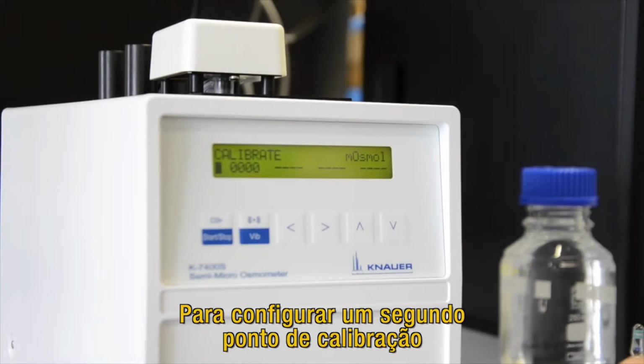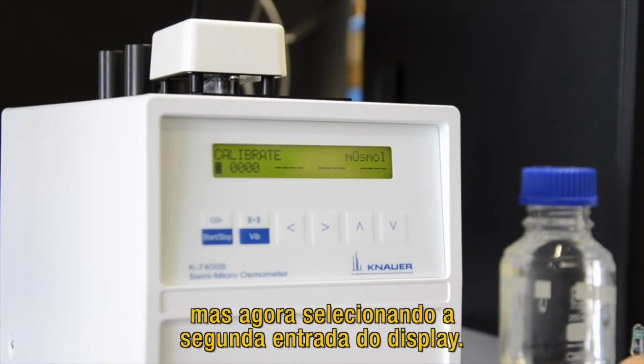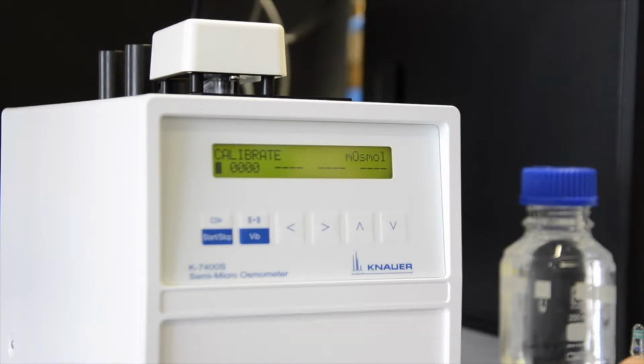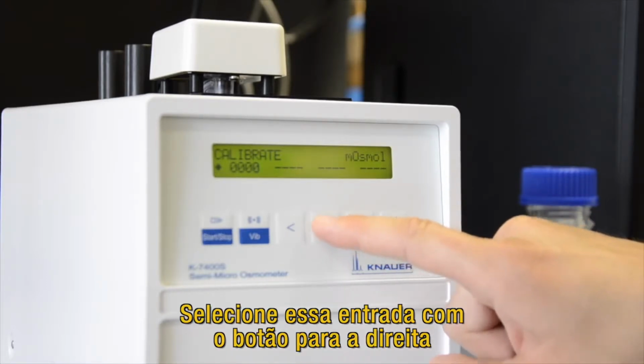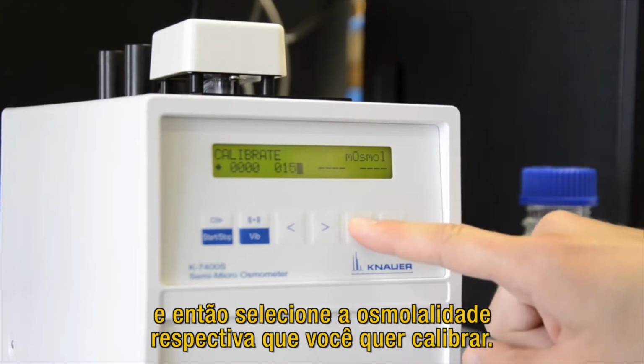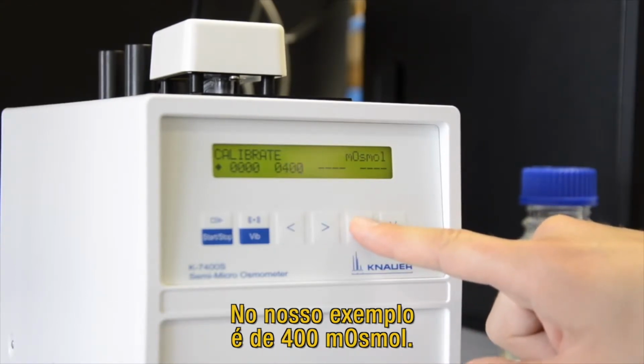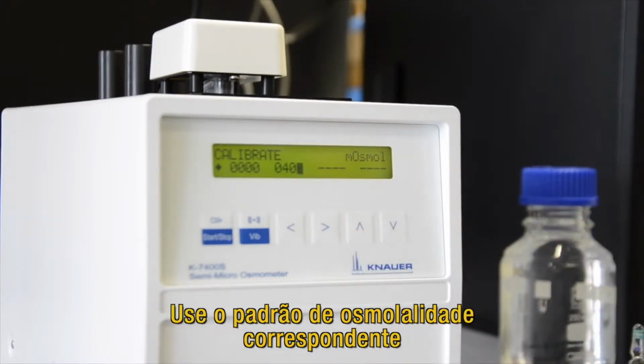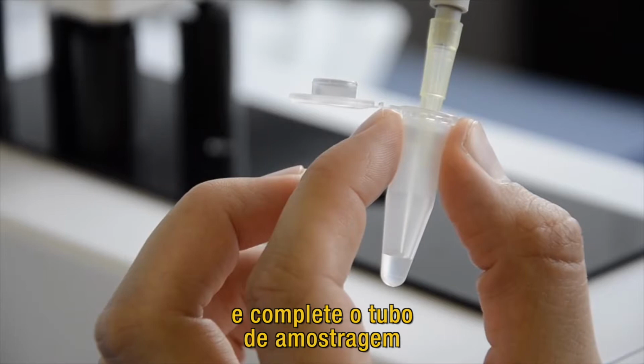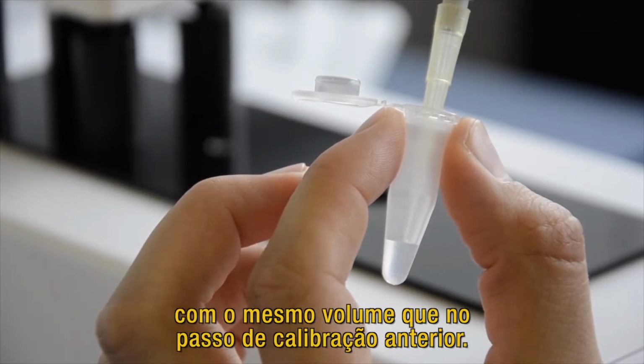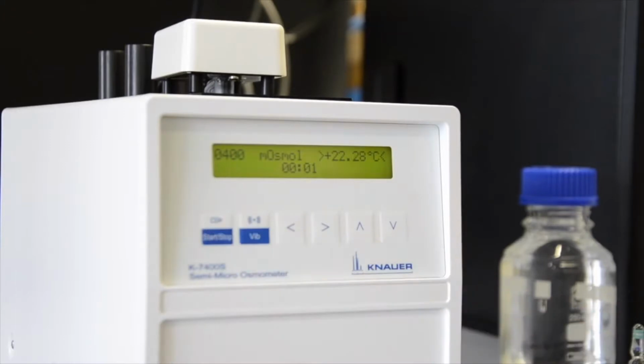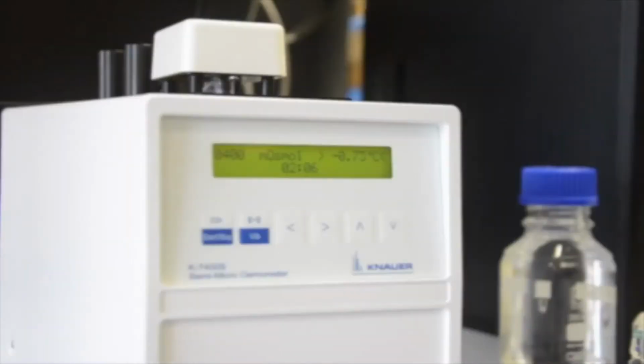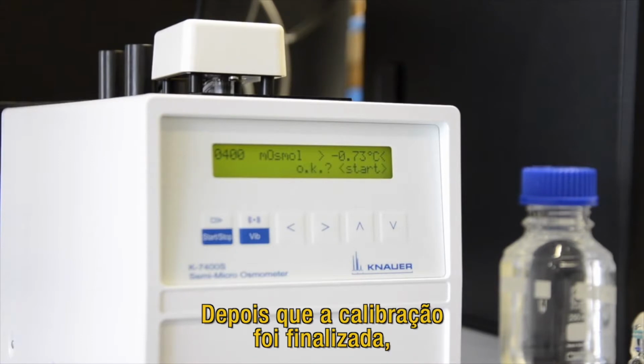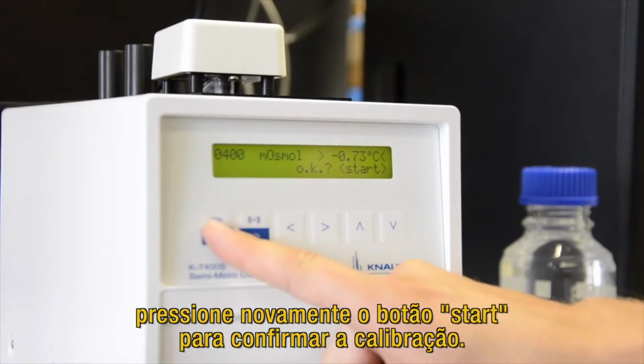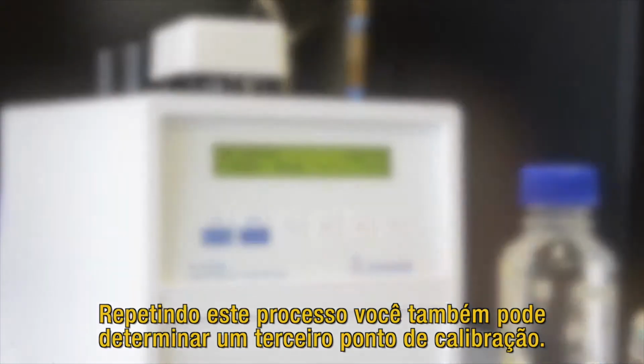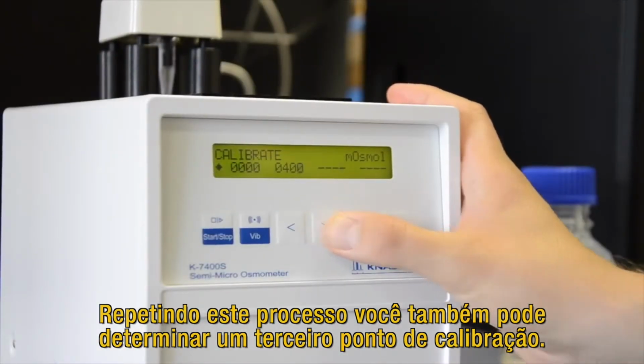To set the second calibration point, you have to do the same procedure again, but now selecting the second entry of the display. Choose it with the right button and then select the respective osmolality you want to calibrate. In our example, this is 400 milliosmol per kilogram. Use the respective osmolality standard and fill the sample tube with the same volume as used in the previous calibration step. After the calibration is finished, press again the start button to confirm the calibration. Repeating this process, you can also set a third calibration point.